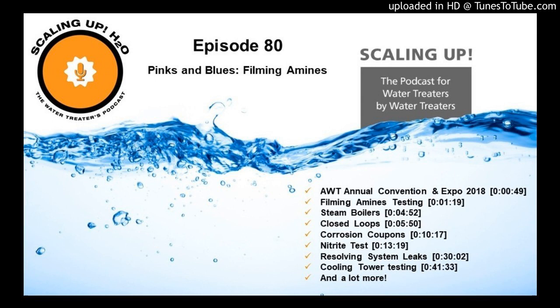But as far as this one goes, I really enjoyed using the Filming Amine product. It is a great cleaner. Of course, our product has some cleaners in it as well. It inhibits differently. We inhibit by that magnetite film, by putting a protective coating once we have that nitrite in the system. Well, this kind of does the same thing, but it does it indiscriminately, which means it's going to coat, it's going to film the entire surface.